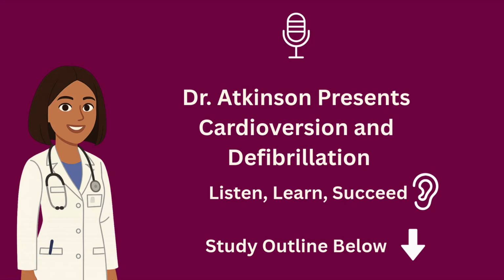Let's take a closer look at cardioversion itself. Electrical cardioversion is a timed shock delivered during the QRS complex to terminate tachyarrhythmias. Synchronization with the QRS is critical because if the shock were delivered during repolarization on the T wave, it could actually trigger ventricular fibrillation. The device must sense the QRS complex, and sometimes the lead or electrode placement has to be adjusted to achieve this. Because of that slight delay, the discharge buttons need to be held down until the shock is actually delivered.